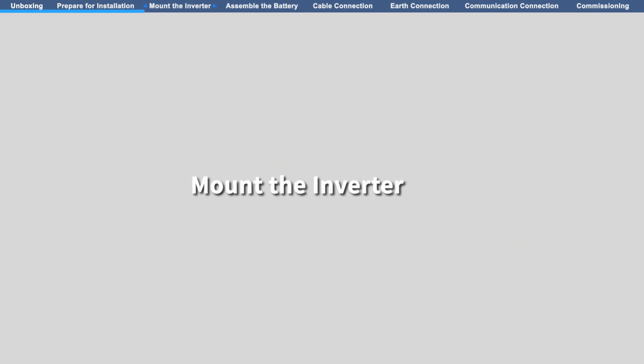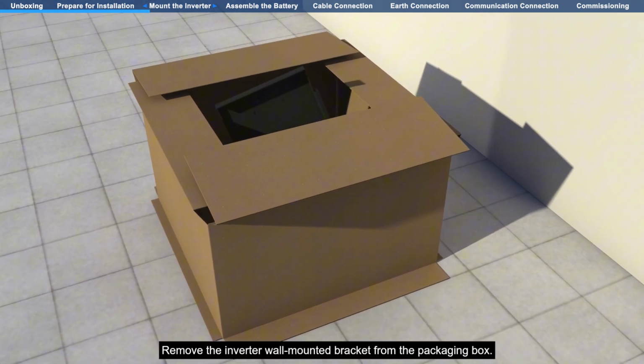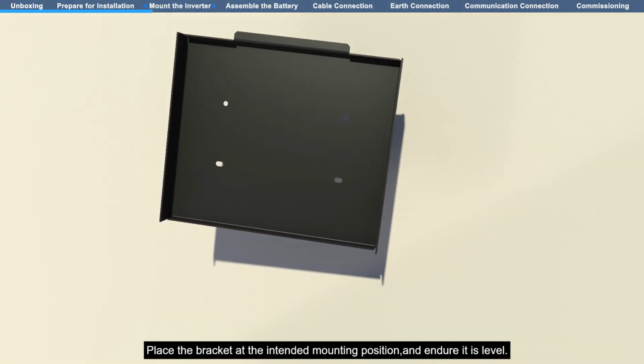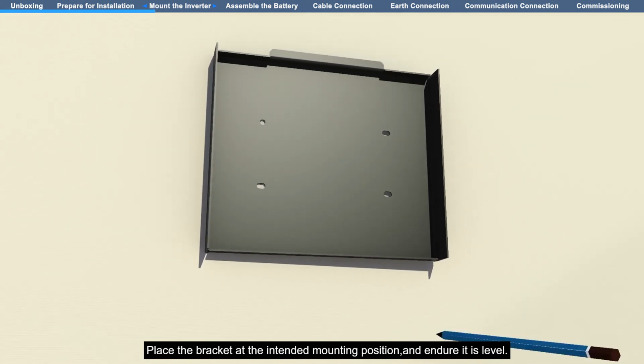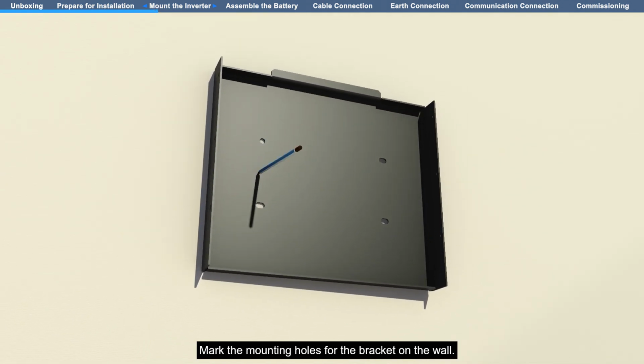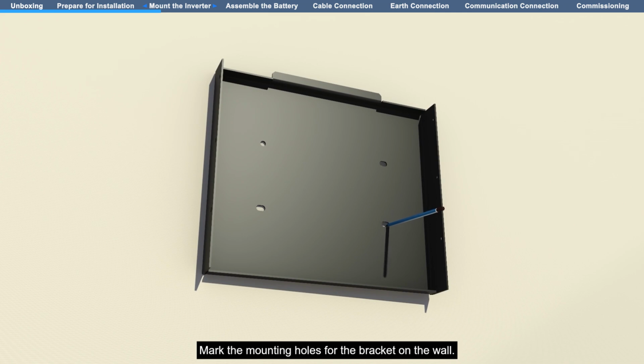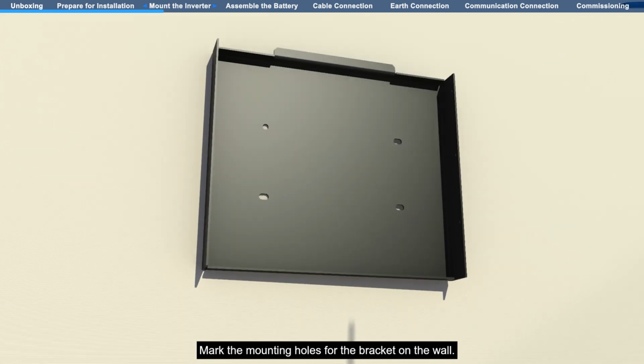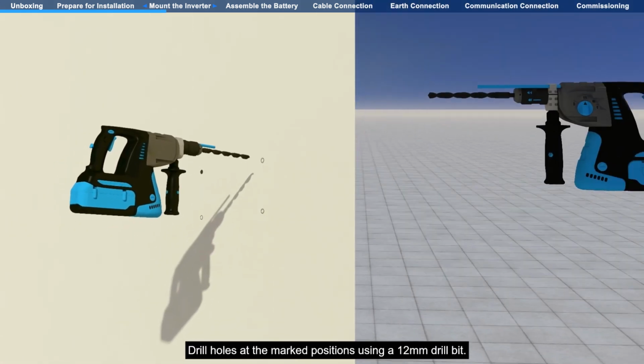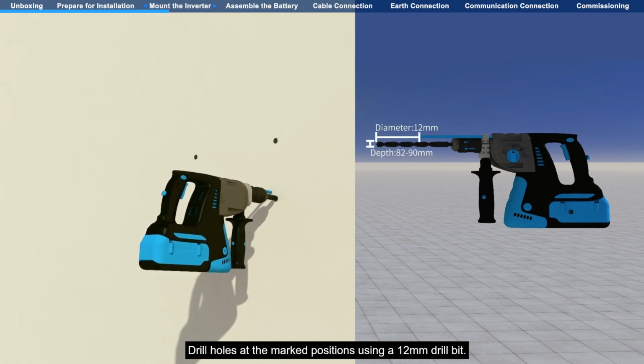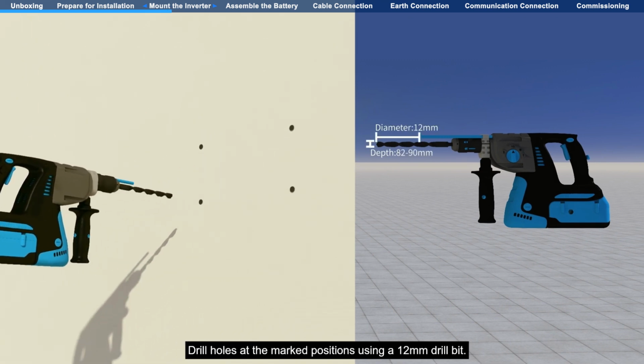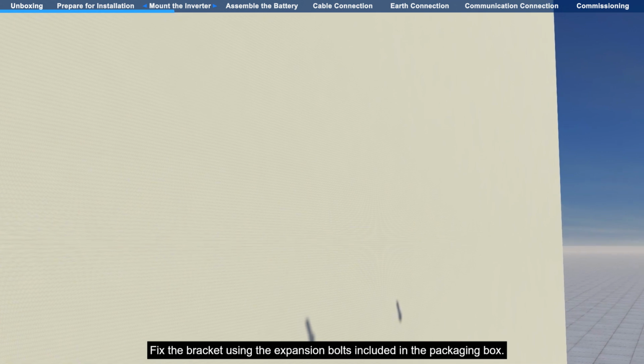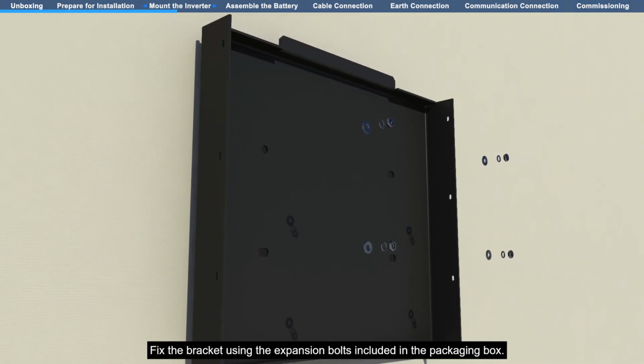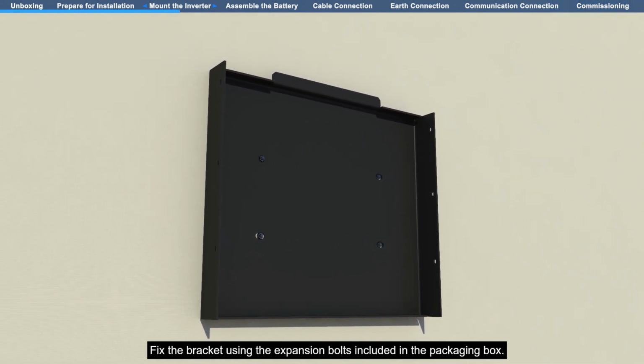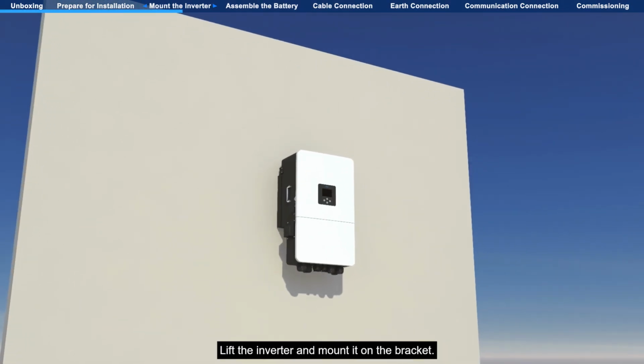Mount the inverter. Remove the inverter wall-mounted bracket from the packaging box. Place the bracket at the intended mounting position and ensure it is level. Mark the mounting holes for the bracket on the wall. Drill holes at the marked positions using a 12 mm drill bit. Fix the bracket using the expansion bolts included in the packaging box. Lift the inverter and mount it on the bracket.